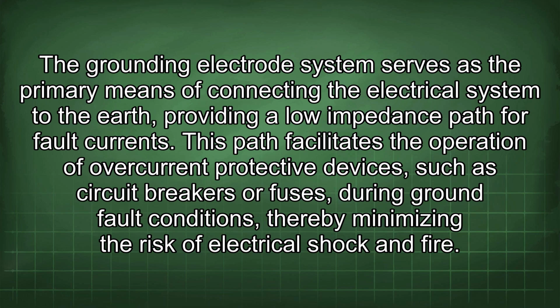The grounding electrode system serves as the primary means of connecting the electrical system to the earth, providing a low impedance path for fault currents. This path facilitates the operation of overcurrent protective devices, such as circuit breakers or fuses, during ground fault conditions, thereby minimizing the risk of electrical shock and fire.